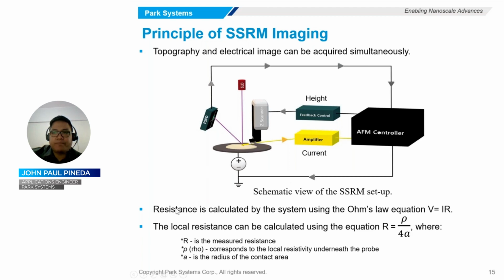So in our setup, the resistance and conductance is calculated by the system using the Ohm's law equation, which is voltage equals current multiplied by the resistance. So this information is displayed in the software to map the electrical properties variation of the surface. By knowing the resistance, one can also calculate the local resistivity by using the equation R = rho over 4a, where R is the measured resistance and rho corresponds to the local resistivity underneath the probe, and a is the radius of the circular contact area. This equation was derived by solving the Laplace equation for the electrostatic potential.